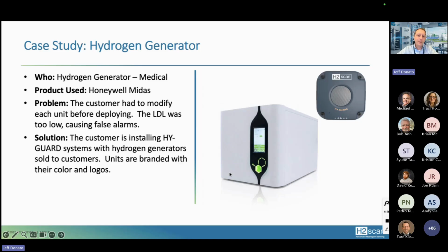You might hear from your customer in area monitoring that, well, the lower the detection limit, the better it is, and that's really not true. We want to have an appropriate detection limit, but we don't want to have something so microscopic that it causes false alarms. And the false alarms is not a defect in the detector. It's just basically what is the threshold that's really needed on site.